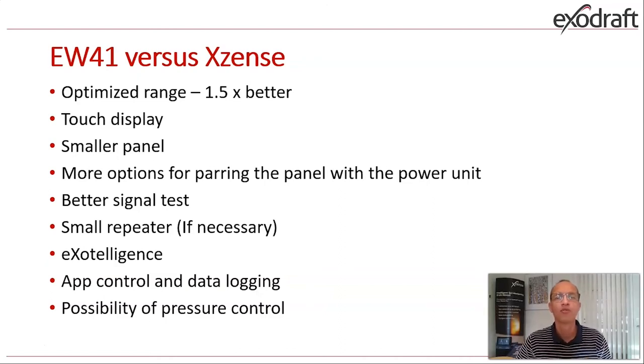If some of you are familiar with the EW41 model that has been on the market for quite some years, this new Xzense has an optimized range — 50% better. We are going from 12 meters to 18 meters of range in normal building construction. The touch display is smaller and much better. We have built in more opportunities for pairing the panel with the power unit, meaning you as a distributor or installer can pair the power unit and the panel in your office before installing at the customer site, using the pin code which is placed inside the box when you buy the product.